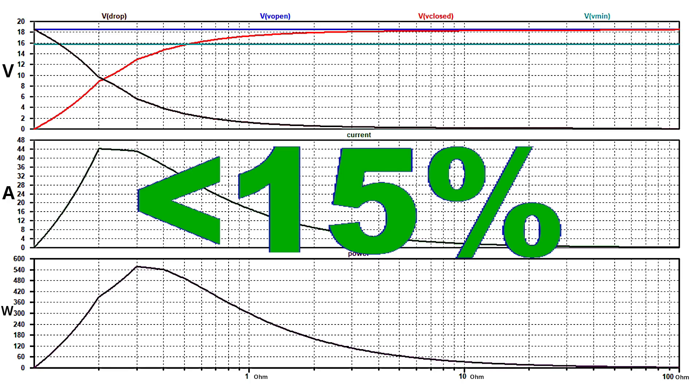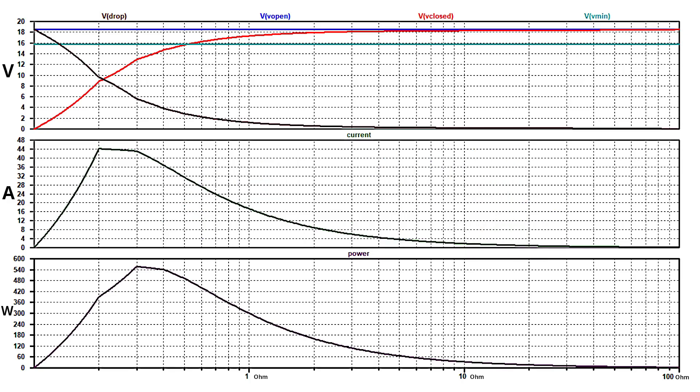As mentioned earlier, for proper operation, the voltage drop with the connected load should not exceed 15% of the no-load voltage. For example, for a no-load voltage of 18.5 volts, it should not drop below 15.725 volts to prevent excessive stress on the transformer.